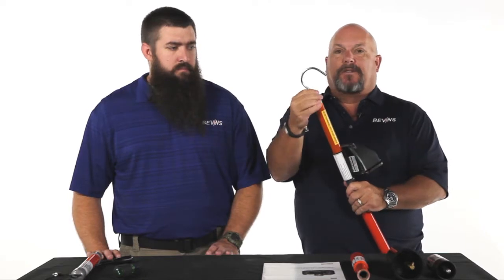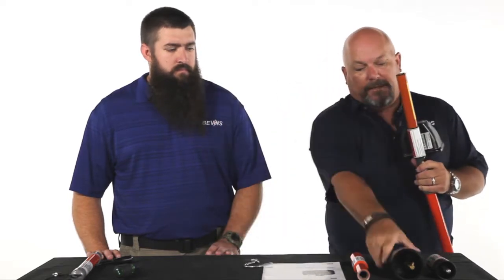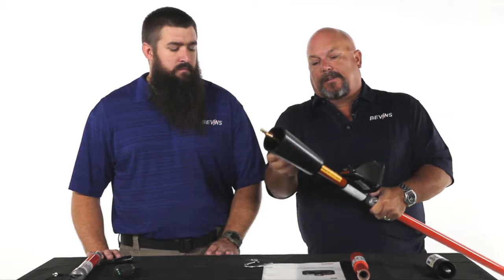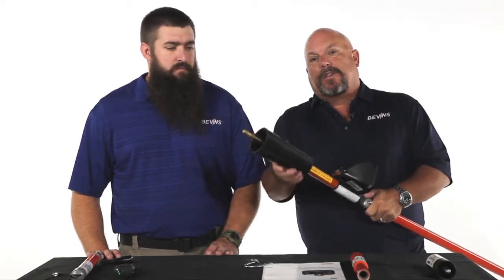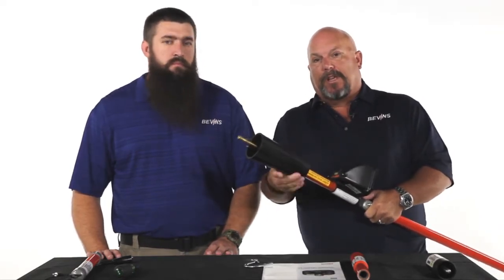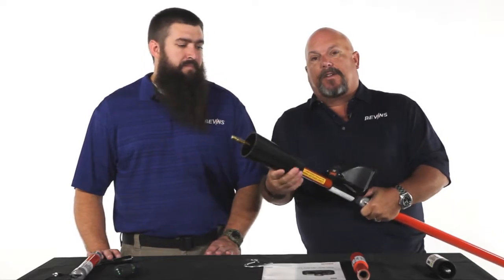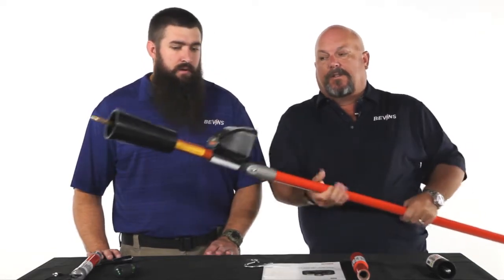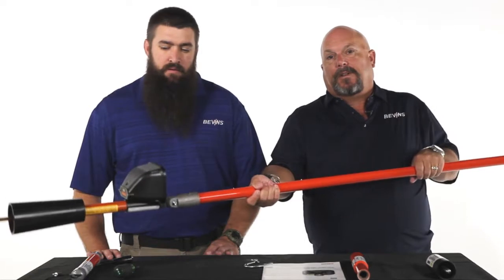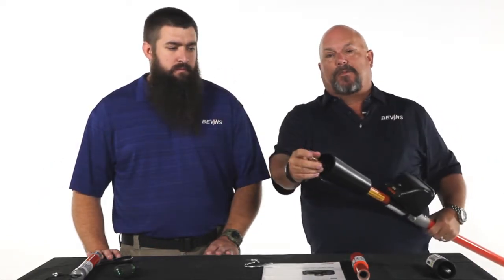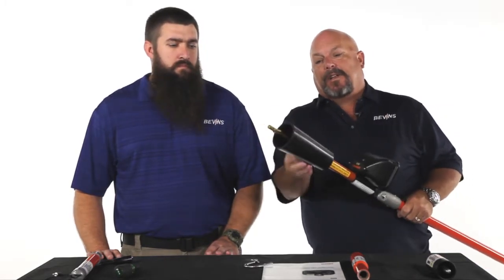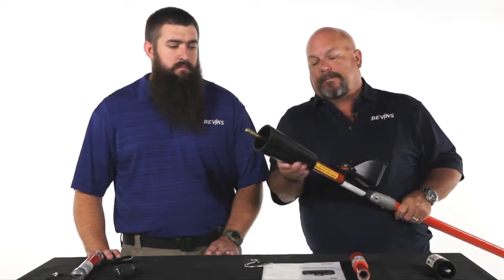That is for your safety completely. It screws right on, as all our adapters and accessories do. And now you're ready for underground. Again, use the minimum approach distance. Never straighten any probe or anything out without the appropriate adapter. You will bring the power outside and can create a flash if you go to ground.